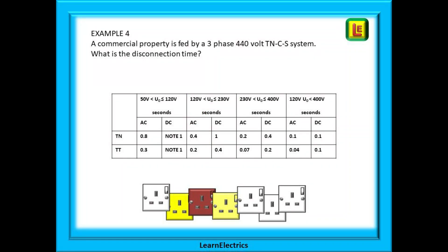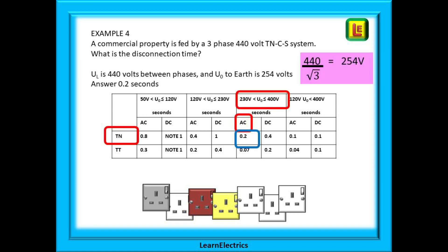The last example, number 4, is another commercial property but this time with a 440 volt TNCS system. First calculate U0 again — the line-to-line voltage is 440 volts. 440 divided by 1.732 gives us 254 volts. 254 volts puts us in the voltage range greater than 230 volts but less than 400 volts, and the answer you should get is a disconnection time of 0.2 seconds.